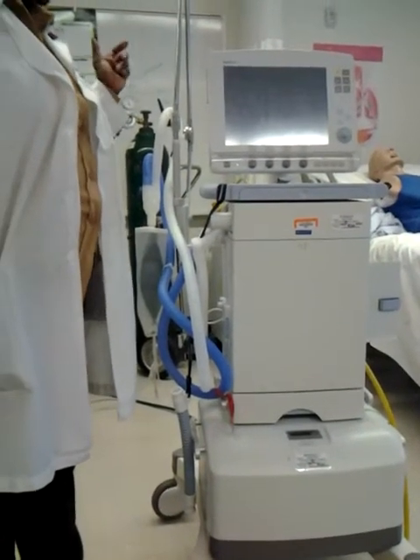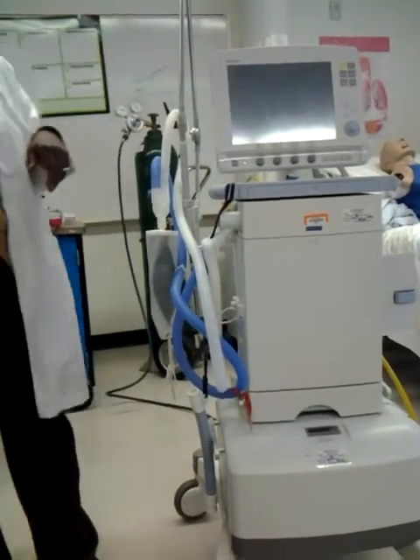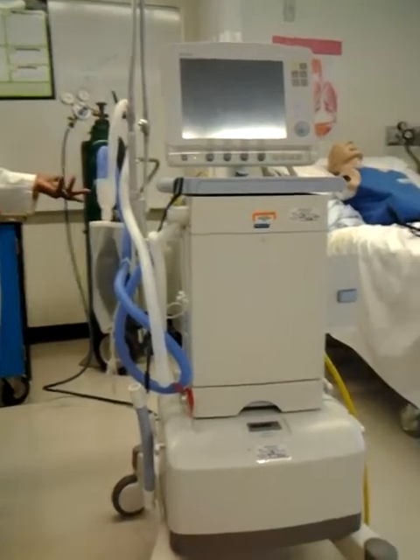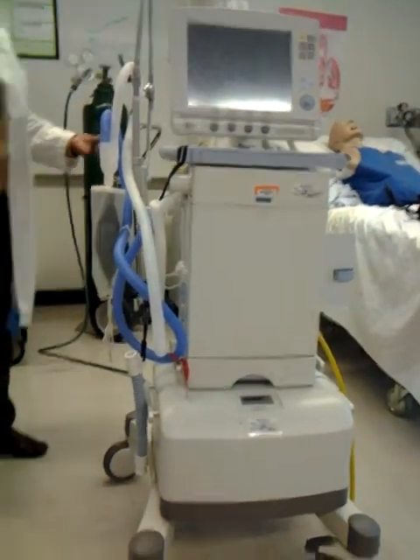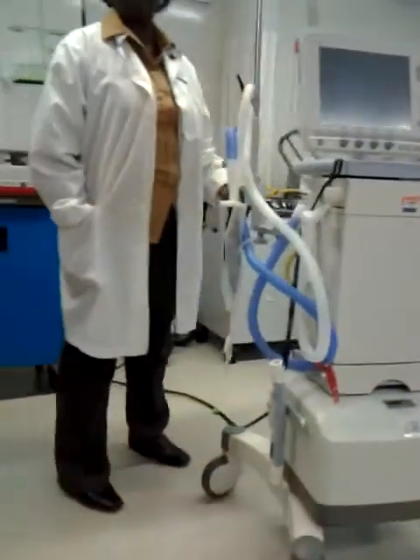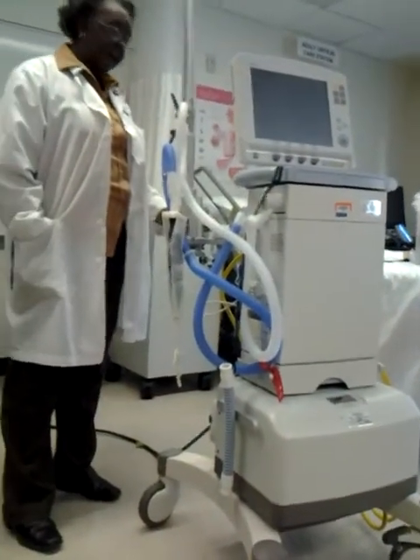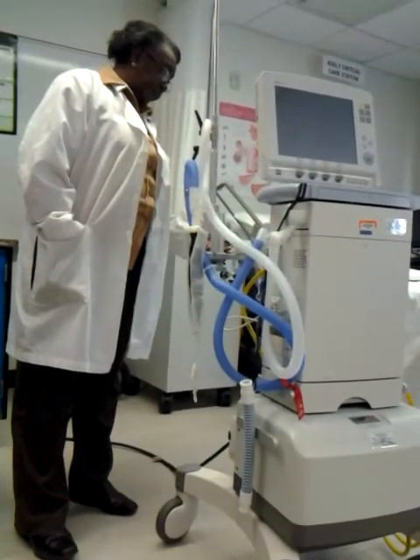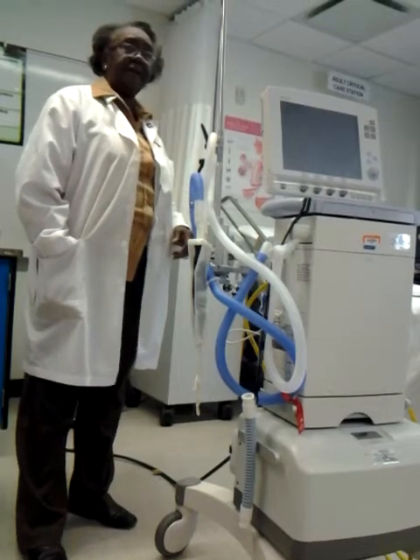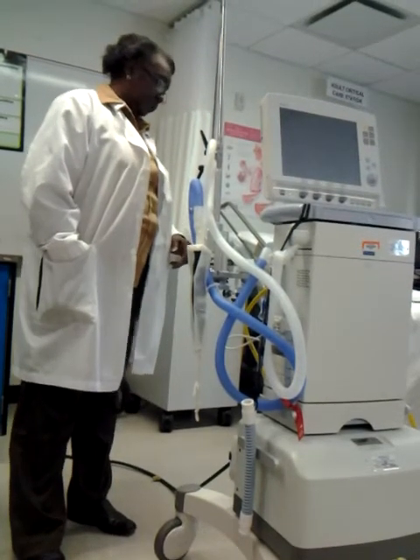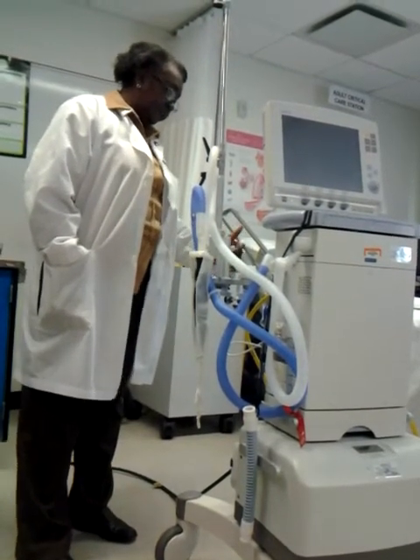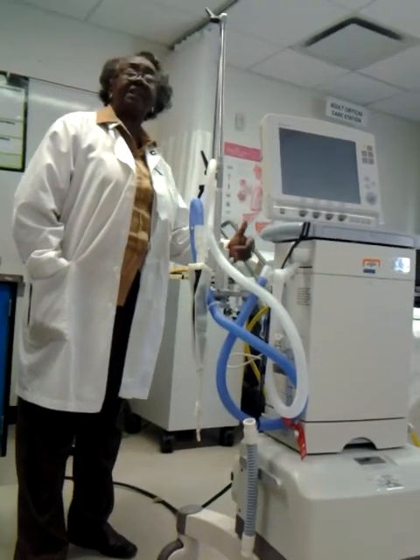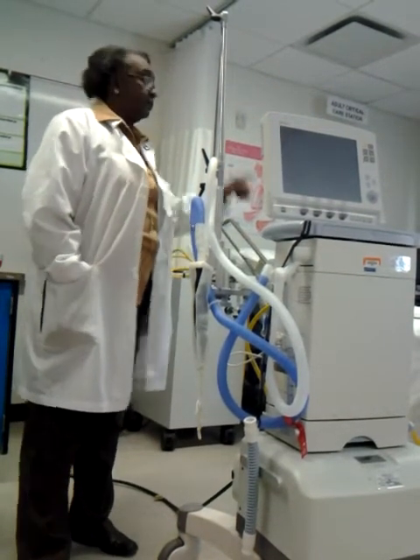Just like the other ventilators. It's electrically powered, pneumatically controlled, so you have to have 50 psi air and oxygen going in. It has its own internal compressor, and if you notice, the guy came in this week and did a service on this machine for us. And you notice the air is actually hooked up from the compressor. You go from the compressor to the wall.